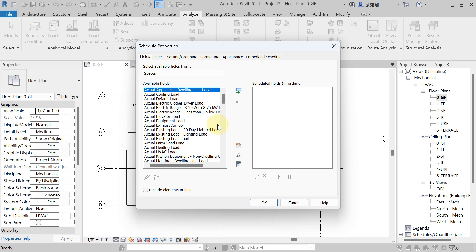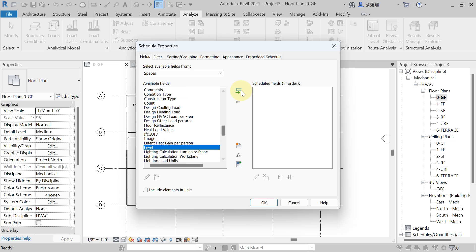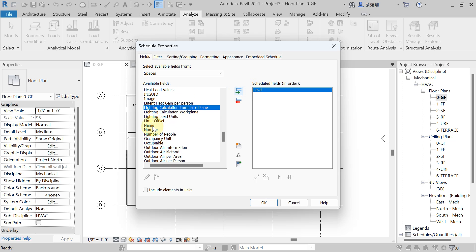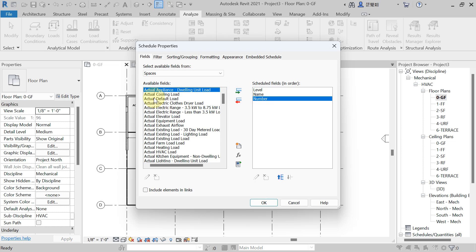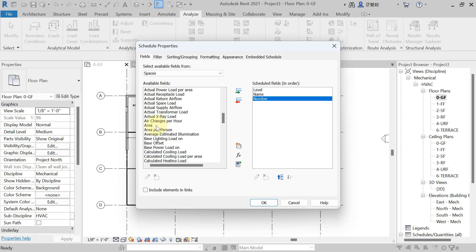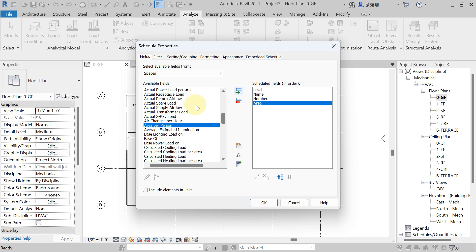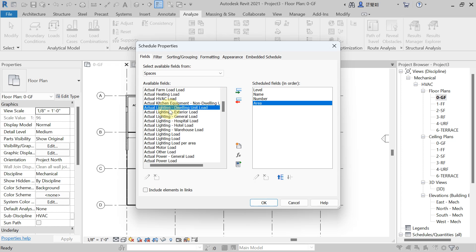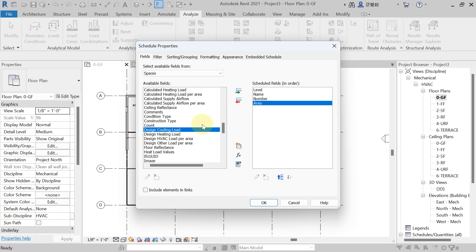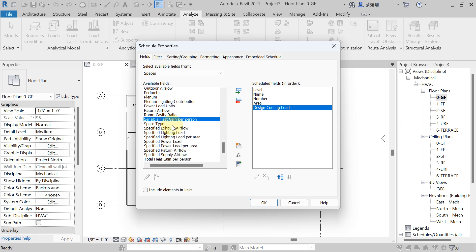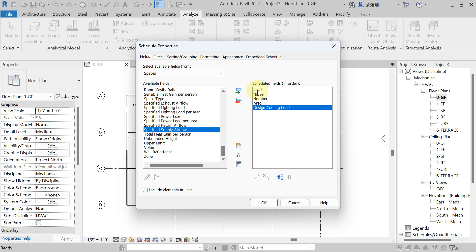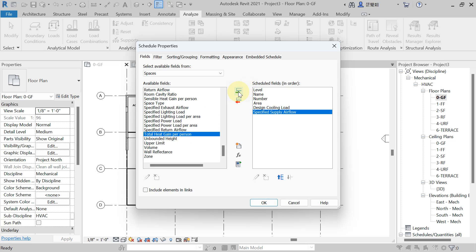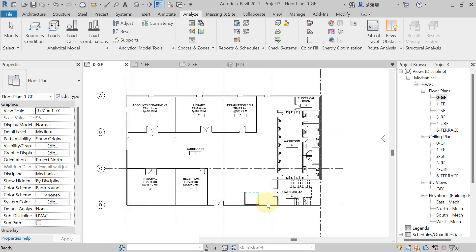Now add the parameters you want to see in the schedule. Add Level, then the space Name and Number. Add Area. Then add Design Cooling Load and Design Heating Load. Also add Specified Supply Air Flow Rate. Add anything else you need, then hit OK.